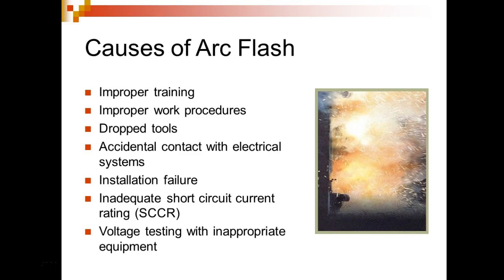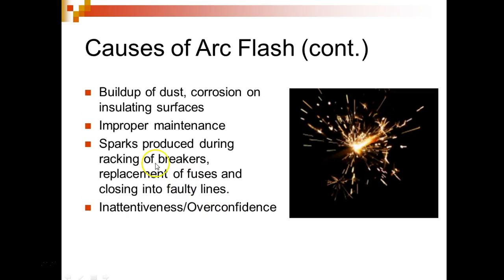Dropped tools, accidental contact with the electrical system, installation failure, inadequate short circuit current ratings, which means not using the right size fuse or breaker. Voltage testing with improper test equipment. This gets a lot of guys in trouble: trying to test voltage and not using the right category meter. Buildup of dust, corrosion on insulating surfaces. This happens a lot in industry where things get dirty, right? And improper maintenance, sparks produced during racking of breakers, replacement of fuses or closing into faulty lines, inattentiveness or overconfidence. This hurts a lot of people too.